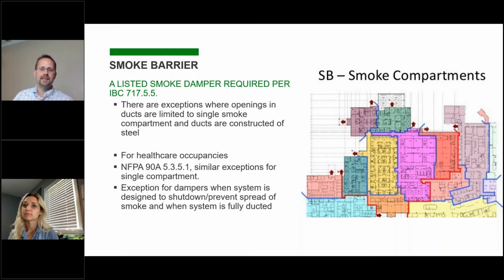But smoke is different, where if you don't have openings, you're running through a smoke barrier, or you have a duct, say for coordination issues, on one side and it runs through that smoke barrier and then comes back through with no openings just to avoid an obstacle. Well, if it just goes through and comes back, no openings, you can avoid a smoke damper at each of those penetrations as well. Obviously, smoke dampers are a lot more cost. They're a lot more difficult in the testing. So we want to avoid smoke dampers as much as we can.